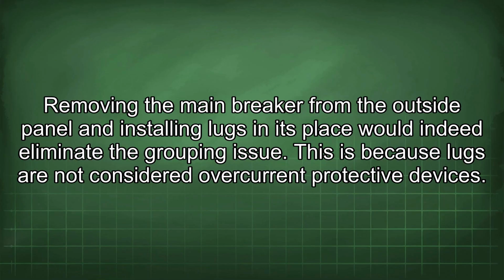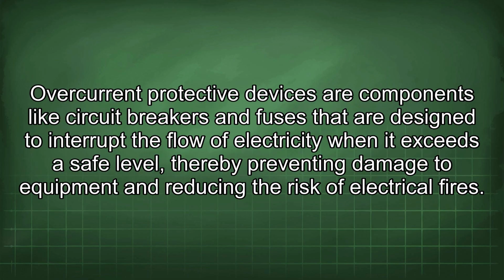Removing the main breaker from the outside panel and installing lugs in its place would indeed eliminate the grouping issue. This is because lugs are not considered overcurrent protective devices. Overcurrent protective devices are components like circuit breakers and fuses that are designed to interrupt the flow of electricity when it exceeds a safe level, thereby preventing damage to equipment and reducing the risk of electrical fires.